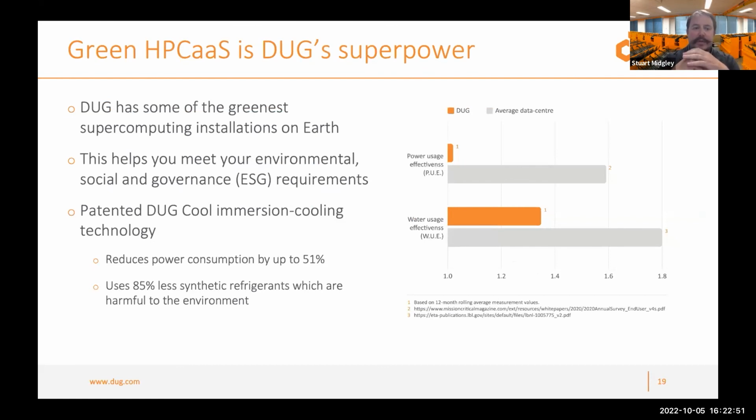The other aspect of immersion cooling is we save a lot of energy, we save a lot of refrigerants, but also we save a lot of water. Most data centers dissipate the heat to the atmosphere in the end through water. They might have refrigeration-based systems, but then they'll couple those to an evaporative cooling-based system to get their efficiency up. So a lot of these data centers pump a lot of water. In Perth here, we don't use much because it's mostly dry cooling, but certainly in our Texas facility, which is our largest, we use a lot of water. But using half the energy means half the energy needs to be dissipated to the atmosphere. So it's a lot less water, which of course will be important in Geraldton.